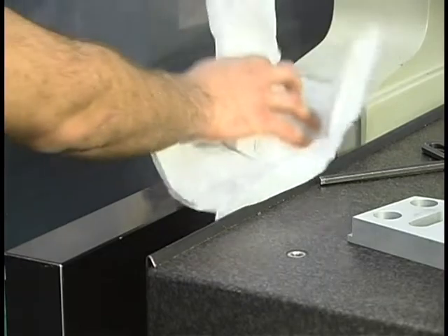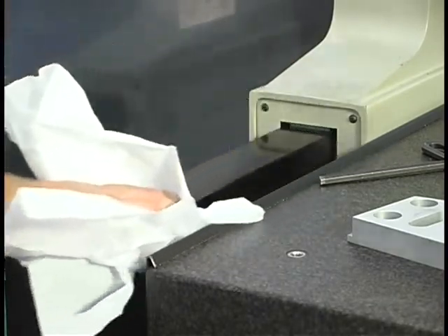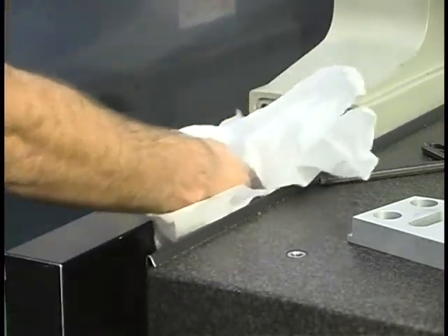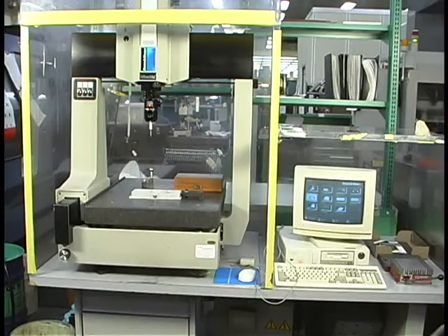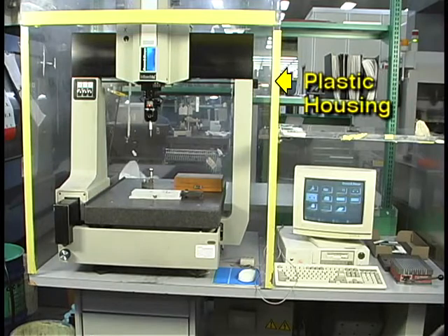Because the air bearing provides only two ten thousandths of an inch of bearing clearance, it is important to keep the ways and the air supply clean and dry. This CMM has been placed in a plastic housing to help reduce contamination from dust and dirt in the shop.